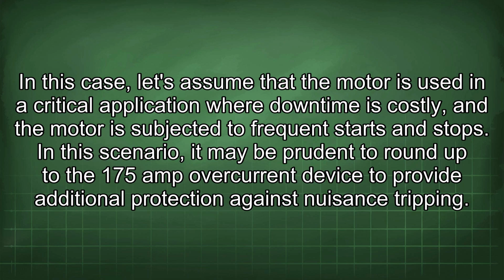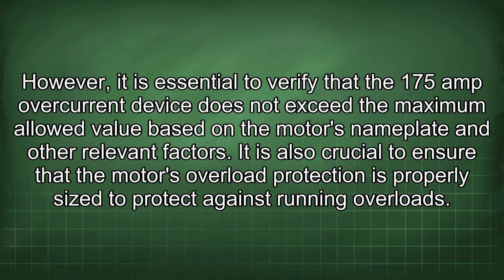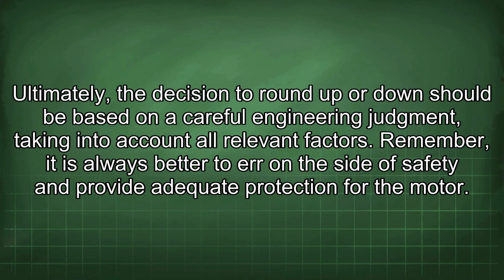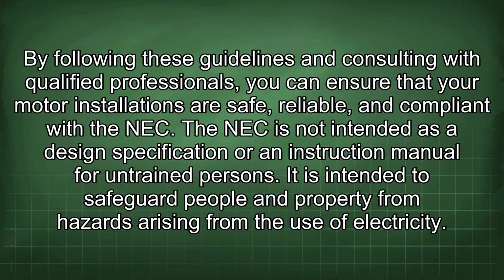In this scenario, it may be prudent to round up to the 175 amp overcurrent device to provide additional protection against nuisance tripping. However, it is essential to verify that the 175 amp overcurrent device does not exceed the maximum allowed value based on the motor's nameplate and other relevant factors. It is also crucial to ensure that the motor's overload protection is properly sized to protect against running overloads. Ultimately, the decision to round up or down should be based on careful engineering judgment, taking into account all relevant factors. Remember, it is always better to err on the side of safety and provide adequate protection for the motor. By following these guidelines and consulting with qualified professionals, you can ensure that your motor installations are safe, reliable, and compliant with the NEC.